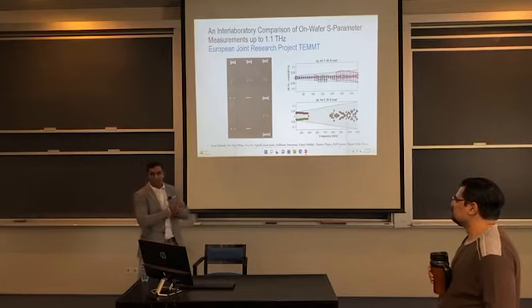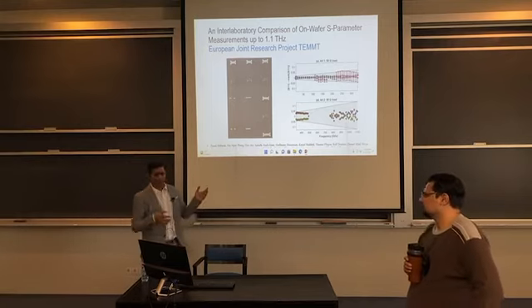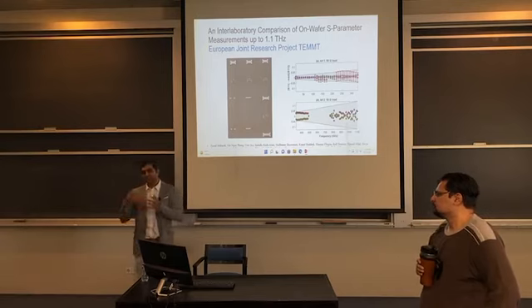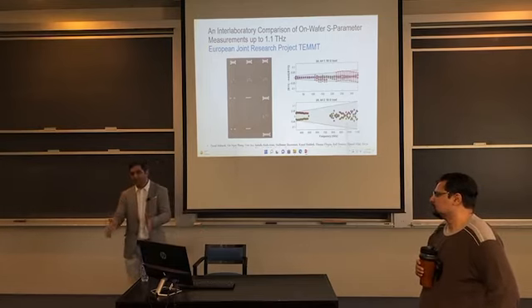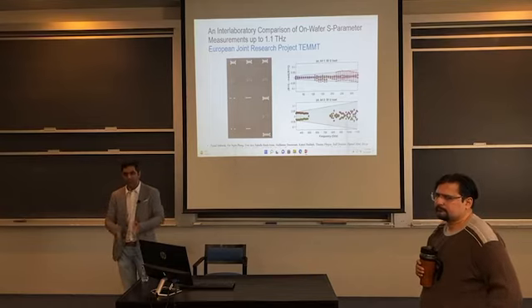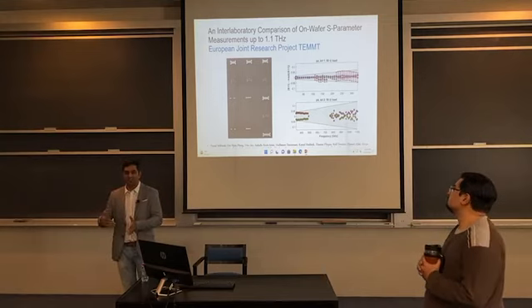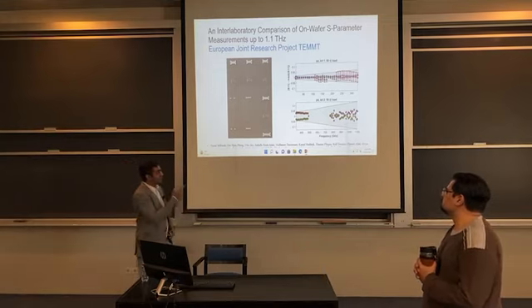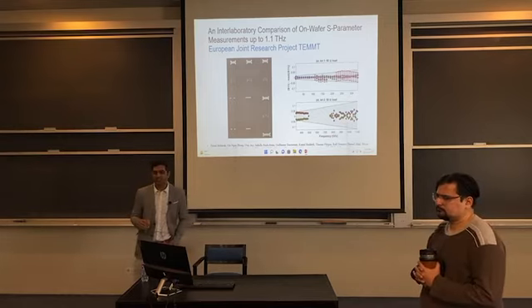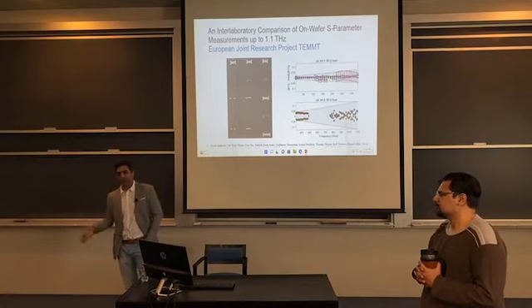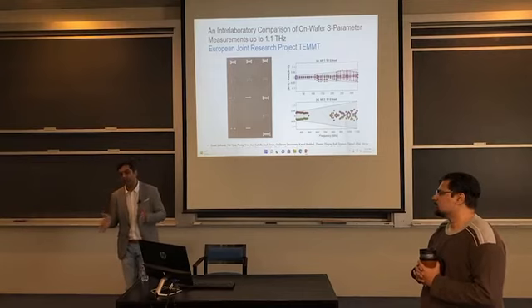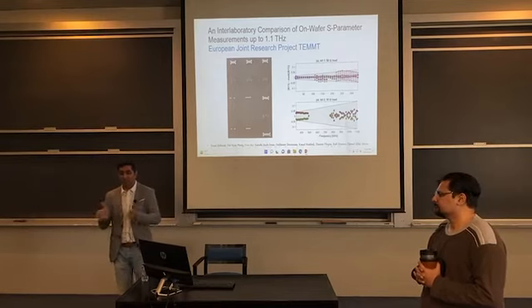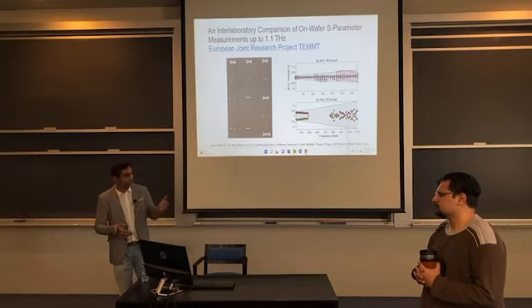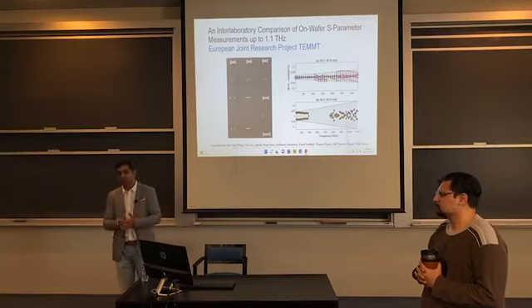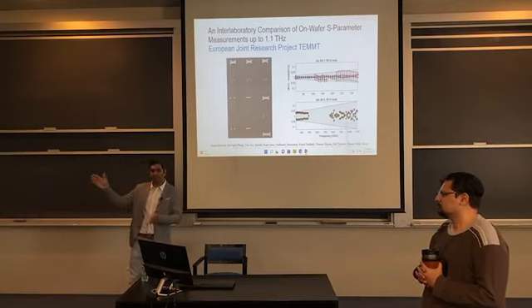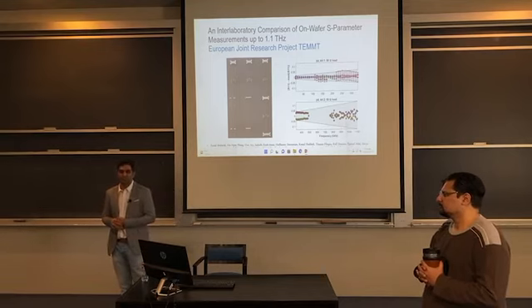And what you are asking for, indeed, for this broadband frequency range, we covered about 6 waveguide bands, which means every time you need to disassemble the system, put on a different frequency extender unit, because we need to switch from one frequency band to another, and repeat the entire calibration measurement process 8 times almost. And that's why it took us about 2 to 3 weeks to make this one graph. It's actually redoing the same measurement for a different frequency band. At this point of time, there's no frequency extender unit that can go from 10 gigahertz to 1.1 terahertz. You need to buy these waveguide bands. One frequency extender goes from 110 to 220, then you go from 220 to 330, 330 to 500, 500 to 750, and 750 to 1.1 terahertz. So it's a lot of repetition.